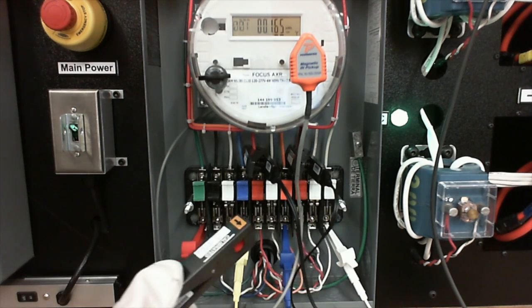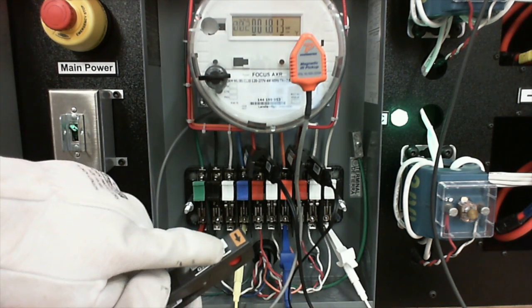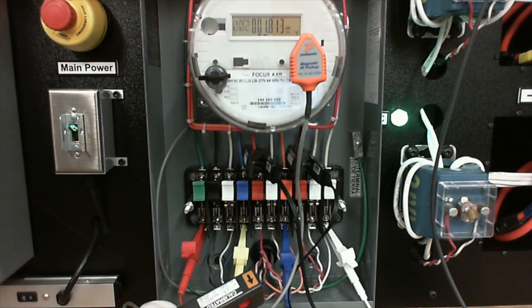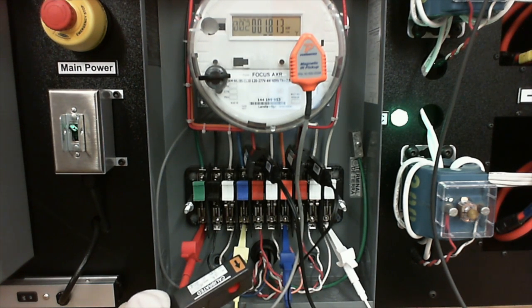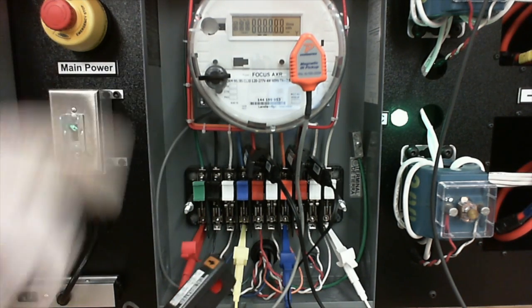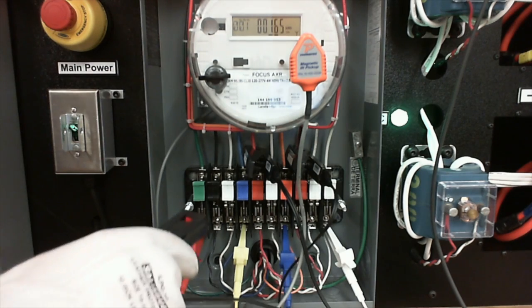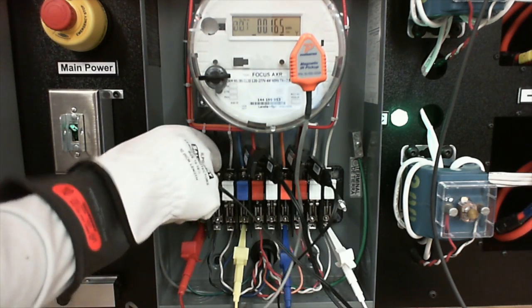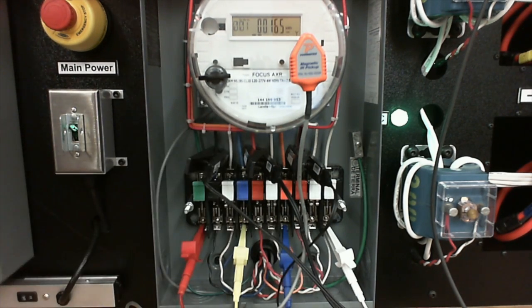These are rated, you can see the arrow, because anything you measure current with has to be directional, since current's directional. My current's coming up through that shunt blade and going up into the meter, so I know my current's going up, so I point the arrow up and put it on like this.